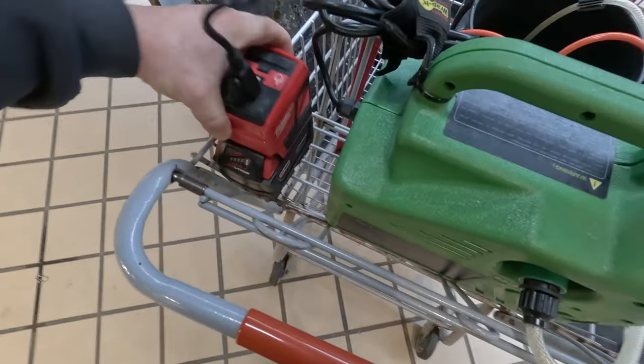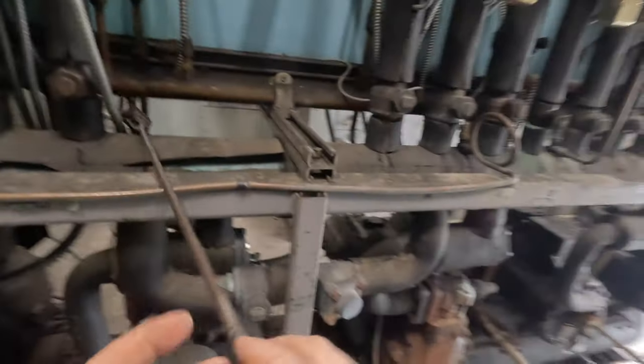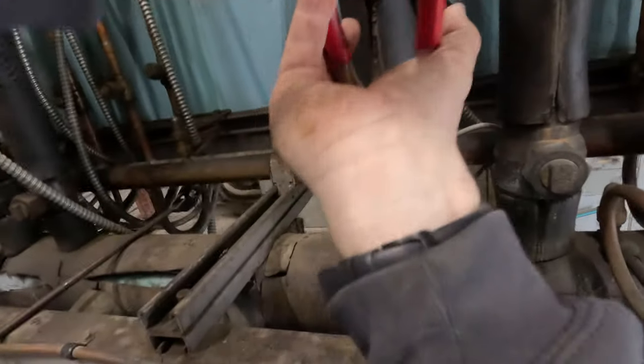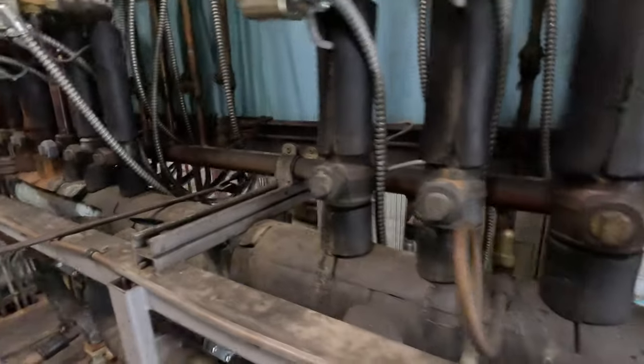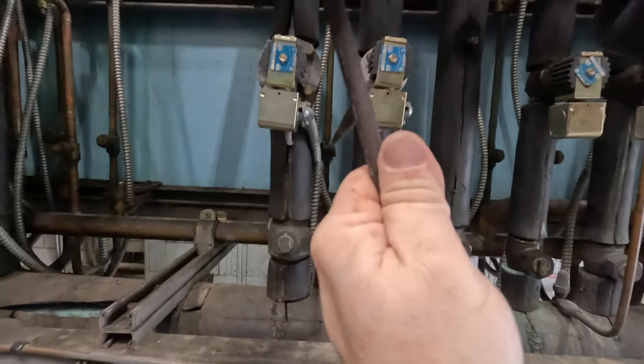When you look at the temperatures of the other cases, it sure appears to me that this was the only one that was acting stupid. We're going to go ahead and get this thing back together. Now, I ran 15 or 20 gallons through this thing, and I only had three bars to begin with, and I'm still at one bar. You guys keep asking — and this is only a 5-amp one. I usually run a 6-amp battery. We're going to go ahead and open up our suction first. There we go. It should start coming up. Then go ahead and turn our liquid on.